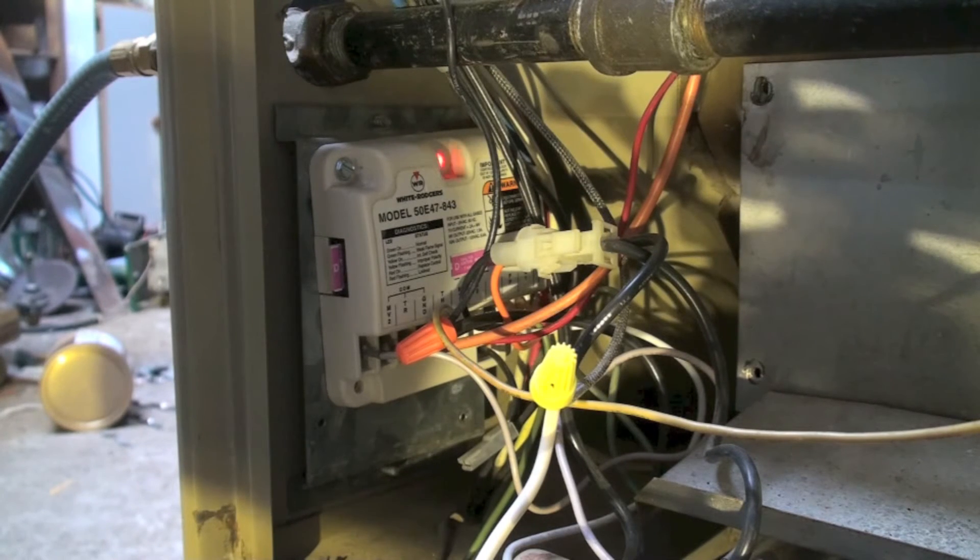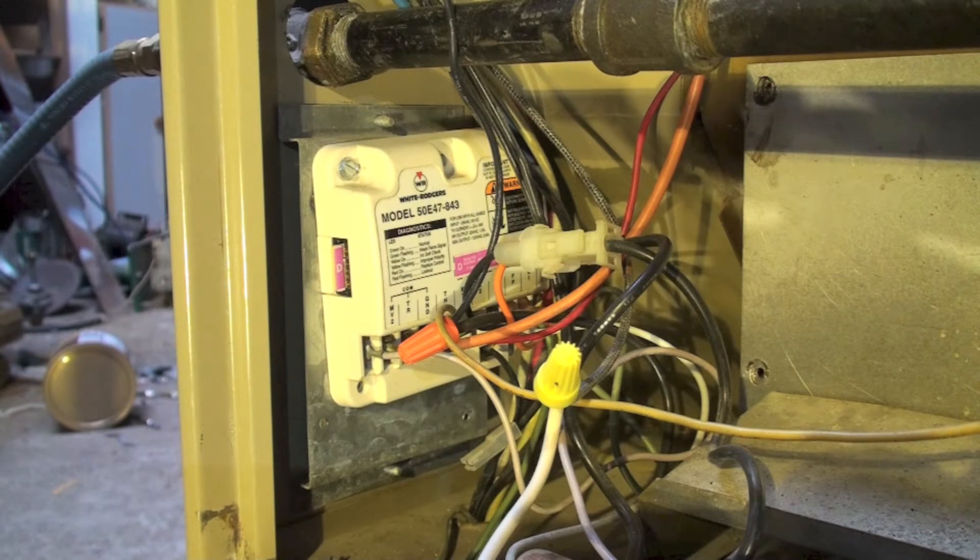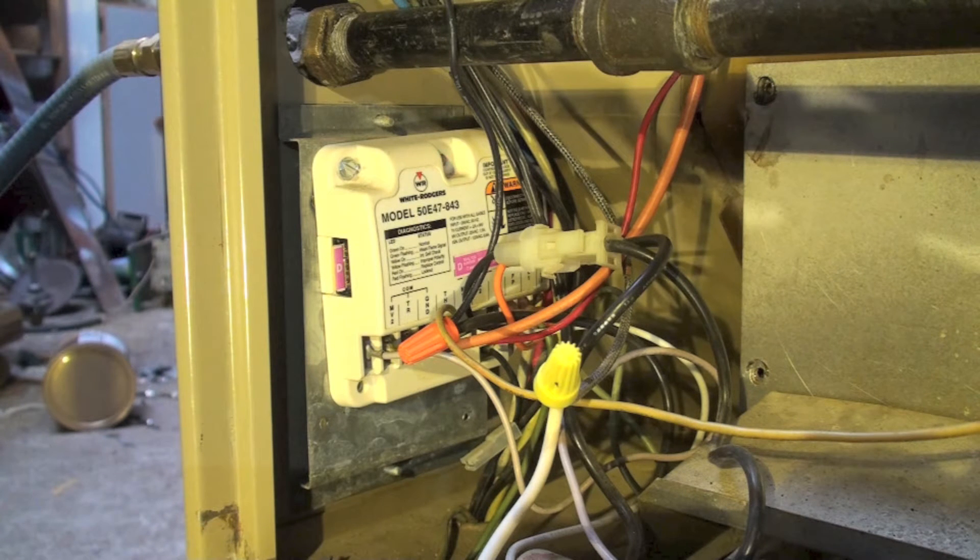Here's my problem: I come down, I can hear the inducer running, the fan's not running, there's no flame, and I have a blinky blinky code. The code is flashing red and that means there's a lockout - didn't sense flame so the system locked out.